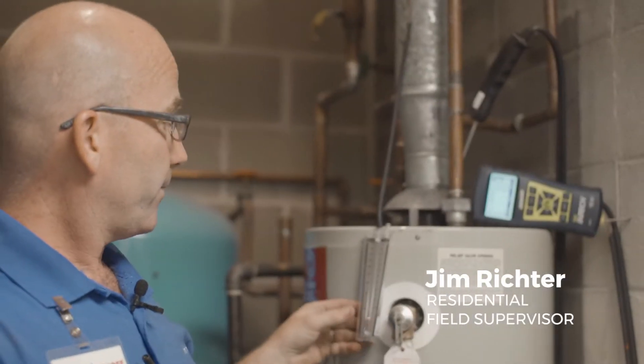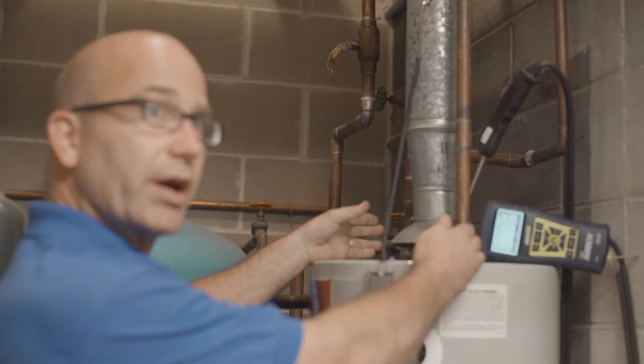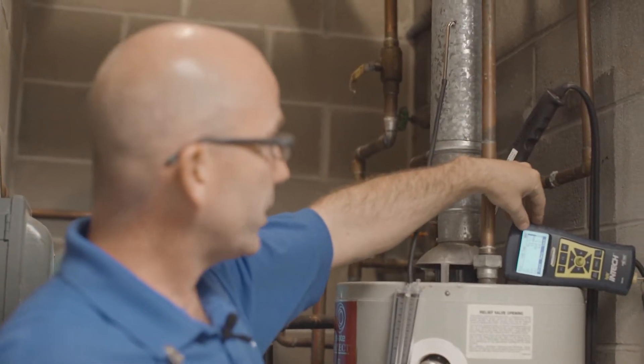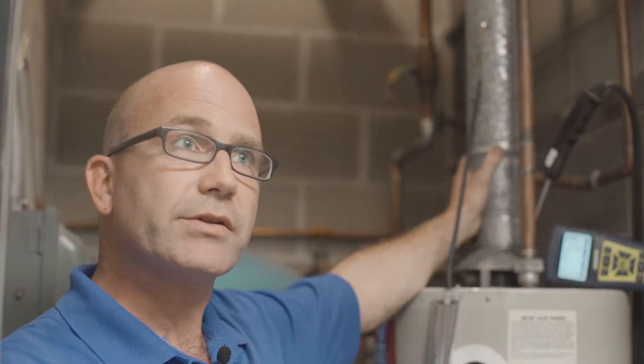So the reason we do the combustion analysis at the same time as the draft, let's say there were no draft and all the flue products are coming out of this draft diverter right here. This number right here is at 23, 24 parts per million, which even if this were not drafting at all and all of it were spilling into the house, that's not enough to cause a health concern.